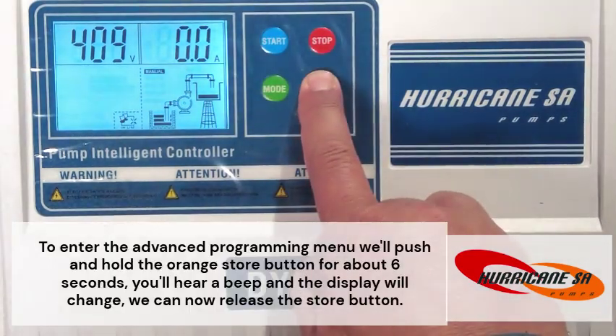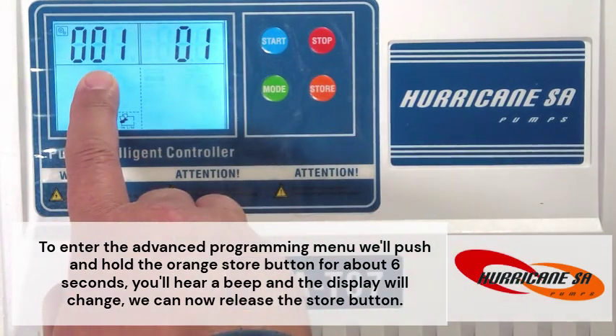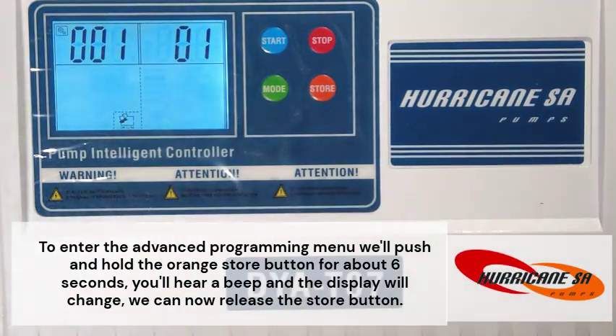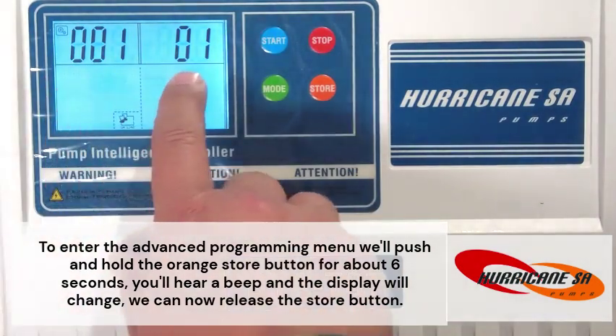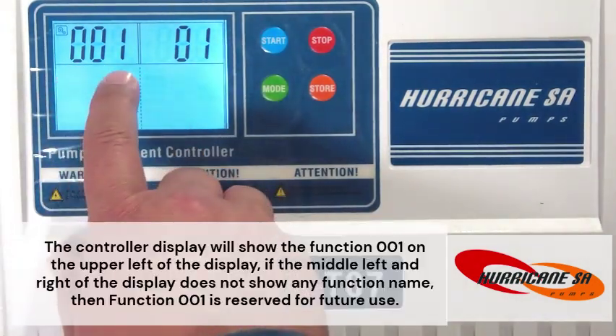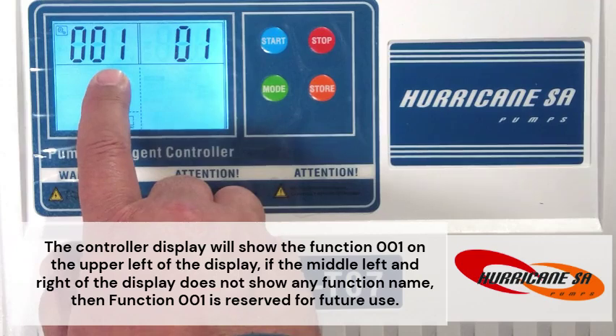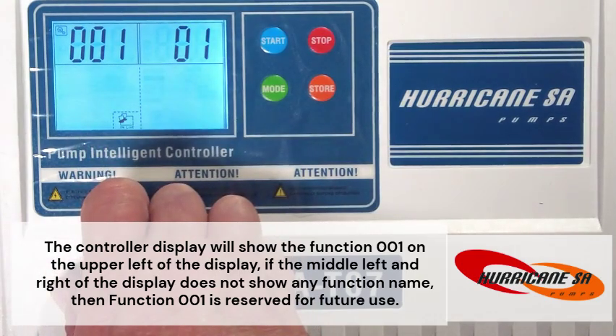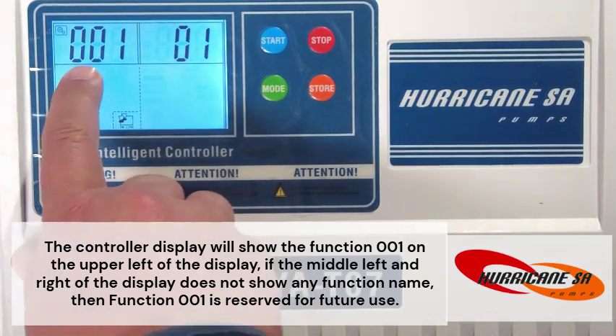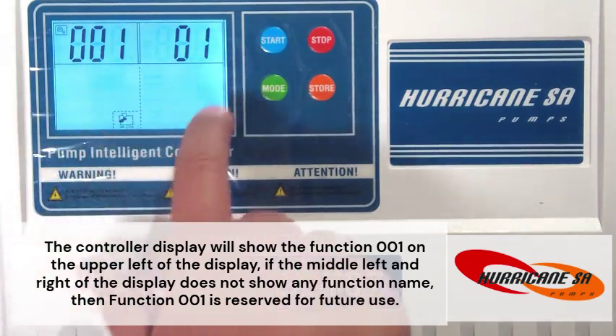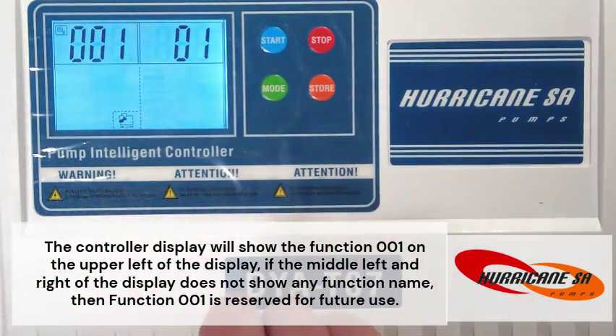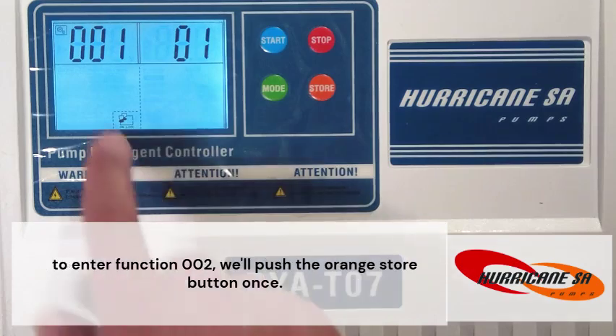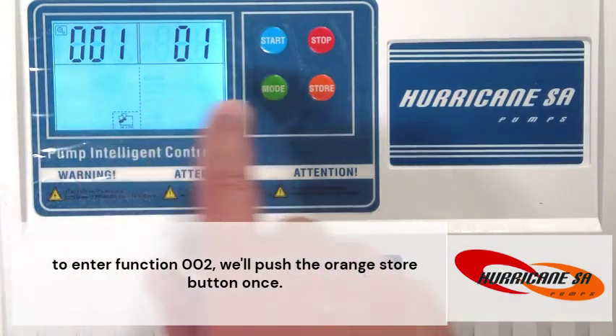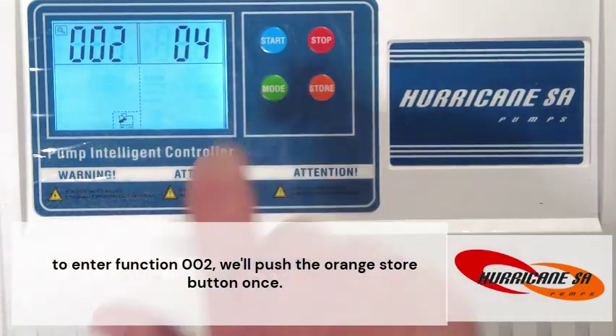To enter the advanced programming menu, we'll push and hold the orange store button for about 6 seconds. You'll hear a beep and the display will change. We can now release the store button. The controller display will show the function 001 on the upper left of the display. If the middle left and right of the display does not show any function name, then function 001 is reserved for future use. To enter function 002, we'll push the orange store button once.